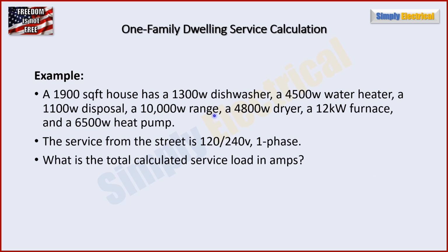Okay, our first example here. Remember, this is a one-family dwelling. This particular one's going to be a 1,900 square foot house. It has a 1,300 watt dishwasher, a 4,500 watt water heater, a 1,100 watt disposal, a 10,000 watt range, a 4,800 watt dryer, a 12 kW furnace, and a 6,500 watt heat pump. The service from the street is 120/240 single phase. That's pretty standard. And now the question is, what is the total calculated service load in amps?